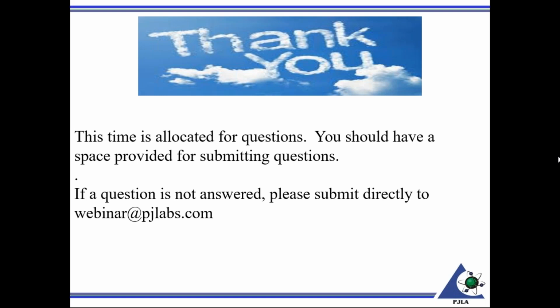Did we need to take all contributors mentioned in the international standard? Not really sure the gist of that question. You have to take into account all significant contributors. Bear in mind, I mentioned those three that I would expect to see in all uncertainty budgets: uncertainty of the standard, repeatability, and uncertainty associated with limited resolution of the device under test. From there, it depends on what's being calibrated.